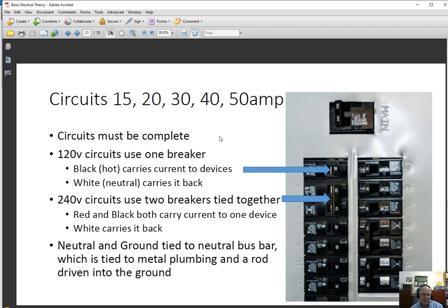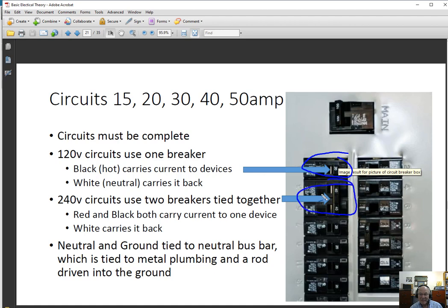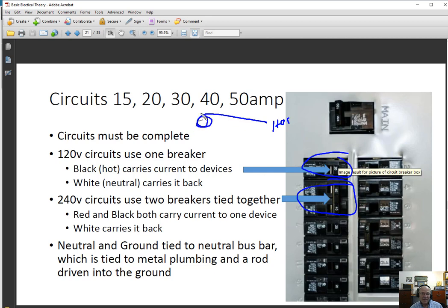120 volt circuits use one breaker. Black carries current to the devices and white neutral carries it back to the service panel. 240 volt circuits use two breakers tied together. There's an example here showing a single 20 amp breaker and a double 40 amp breaker, which is probably providing current to an electric stove. The neutral and the ground are both tied together because the ground is actually just an alternative to the neutral.